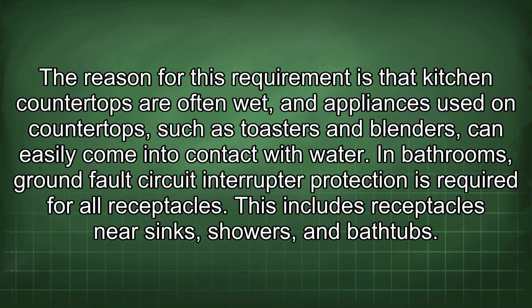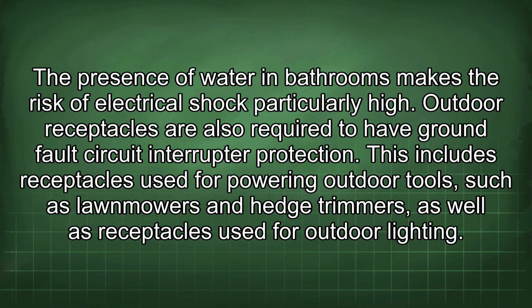The reason for this requirement is that kitchen countertops are often wet, and appliances used on countertops, such as toasters and blenders, can easily come into contact with water. In bathrooms, ground fault circuit interrupter protection is required for all receptacles. This includes receptacles near sinks, showers, and bathtubs. The presence of water in bathrooms makes the risk of electrical shock particularly high.